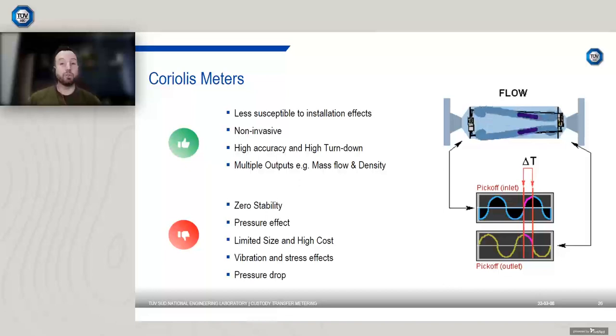Another disadvantage is Coriolis meters have a well-documented pressure effect. So when the pressure of your fluid changes, that affects the stiffness of the measuring tubes, and that's going to affect how they twist when you've got flow going through the meter. So you need to account for that because the effect can be quite significant. Now, the good thing is the effect is fairly linear, so you can correct for it, or even better, if you calibrate at your operating conditions. So at NEL, we've got our elevated pressure and temperature facility. Primarily, this was designed to calibrate Coriolis meters at service conditions, so you can calibrate out the pressure effect, but it does have to be considered.